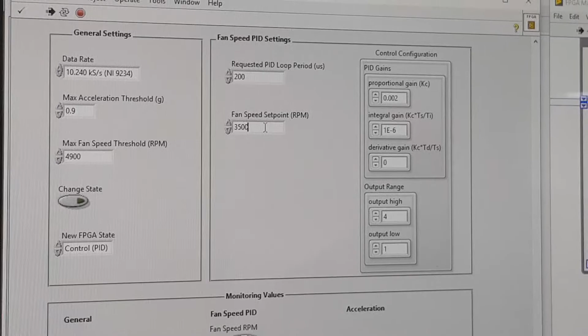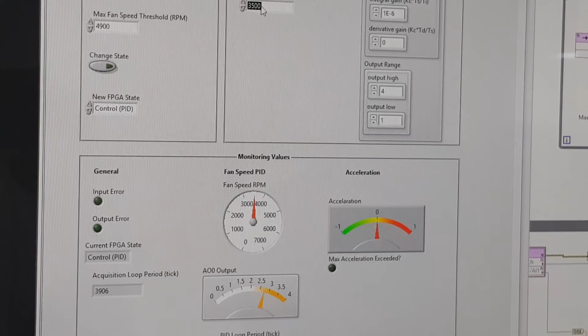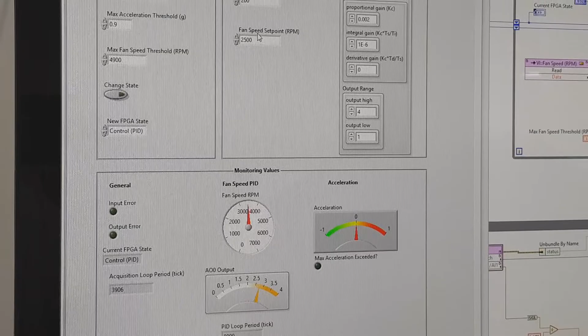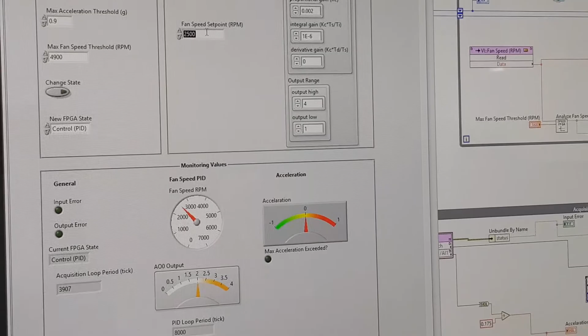4000 means it should increase the analog output voltage. You should notice that if it is 3500, the analog output voltage should decrease. Now see, it decreased. If I make it 2500, the analog output voltage should decrease so that this set point is achieved. When I click enter, you see the voltage is decreasing, and vice versa. If I increase it, the output voltage should increase.